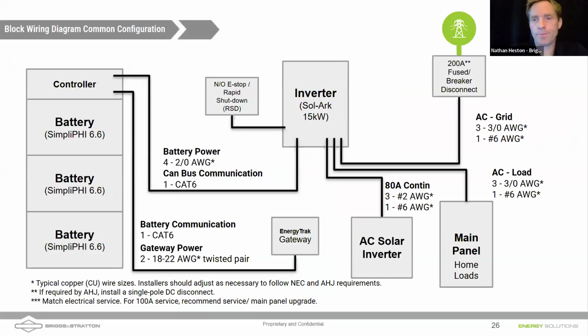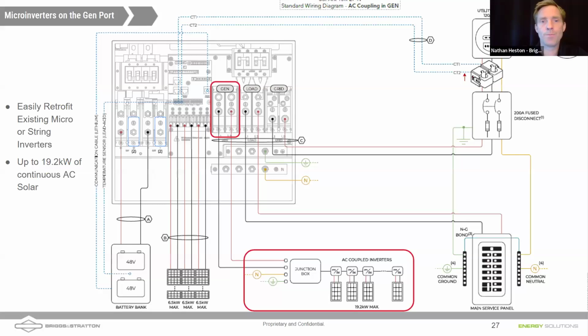Daniel, what are we looking at here? The single line diagram, again, we have a Sol-Ark 15K here with the 200 amps coming in, 200 amps going back out to that main panel, the home loads. We have our AC coupled solar here. We don't have any DC coupled solar in this example here. We got a single stack of three 6.6 batteries, bringing the power over into the Sol-Ark. Yeah, and so we're recommending some wire sizes. Of course, the lengths of your wire runs can influence this, but to try to give you a simple idea of what an AC coupled system looks like with the Sol-Ark 15K here.